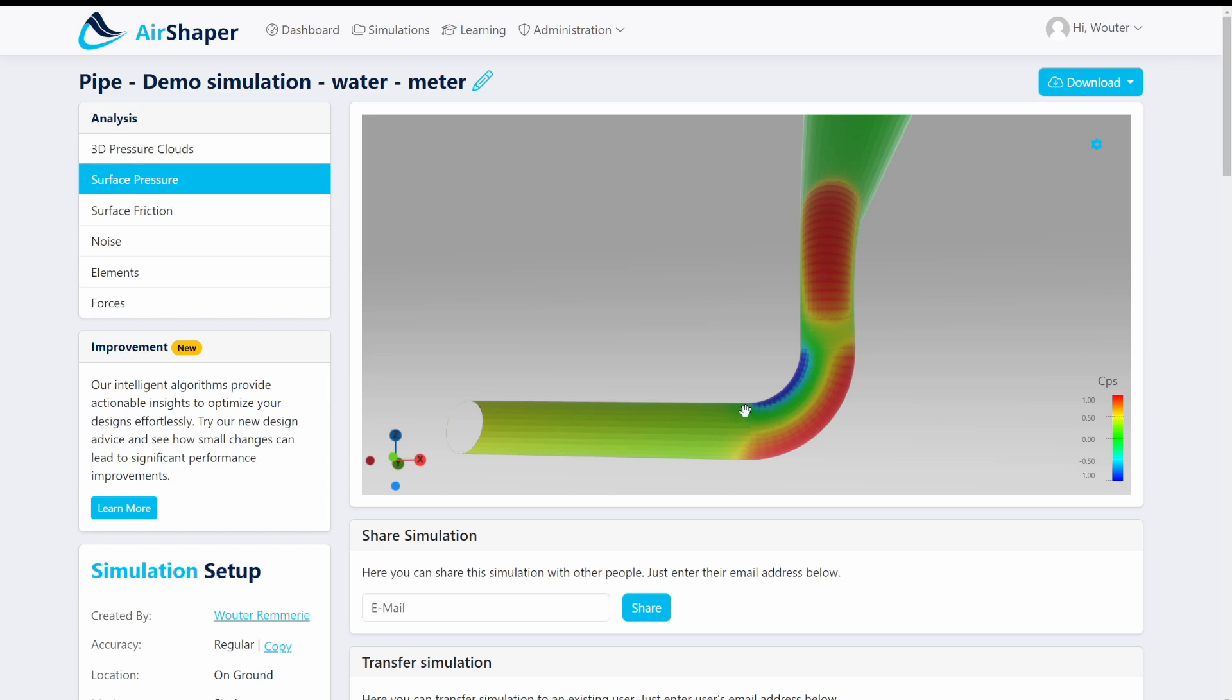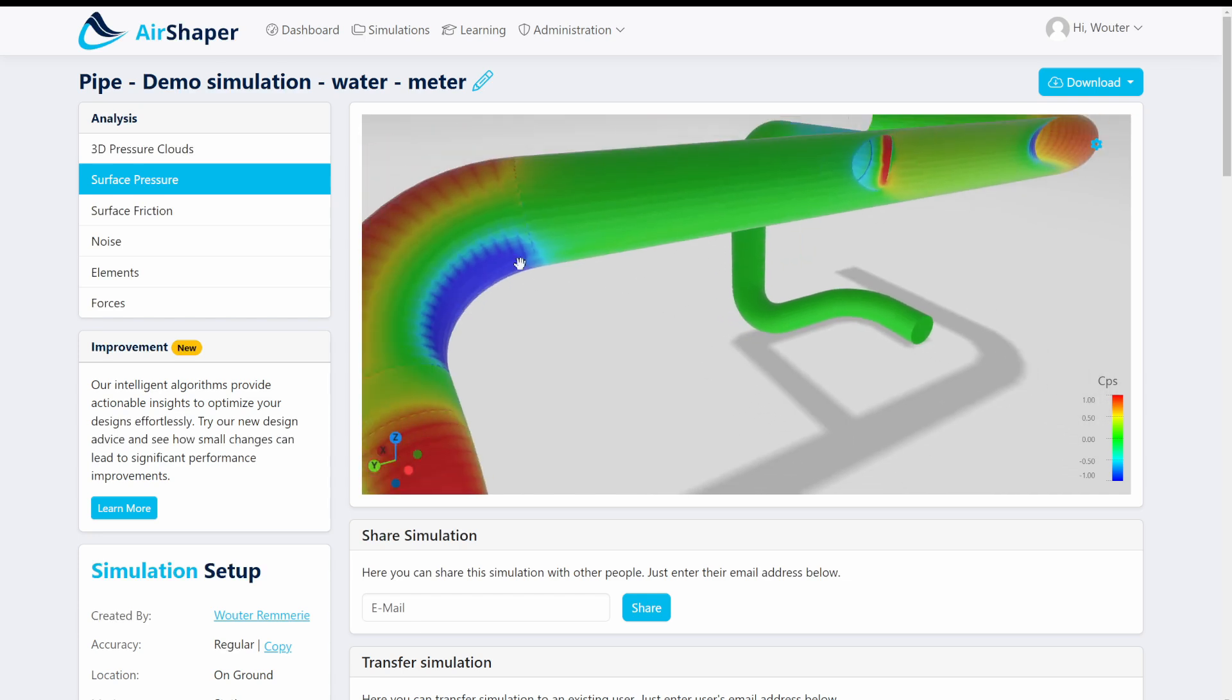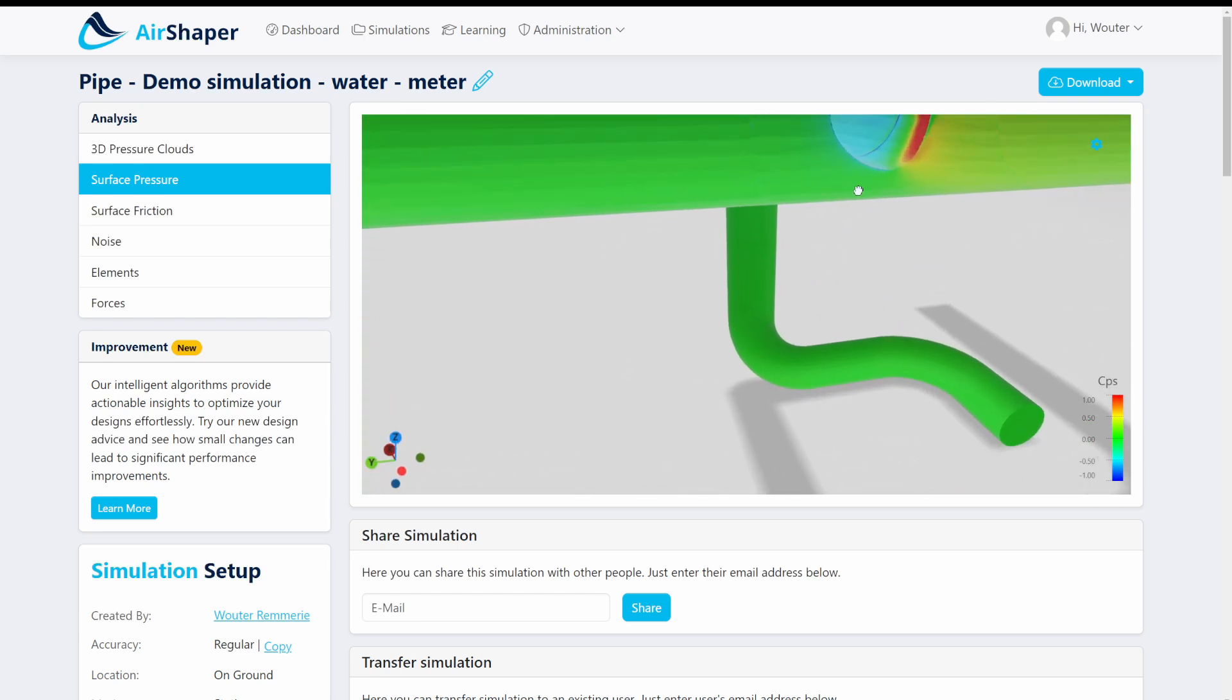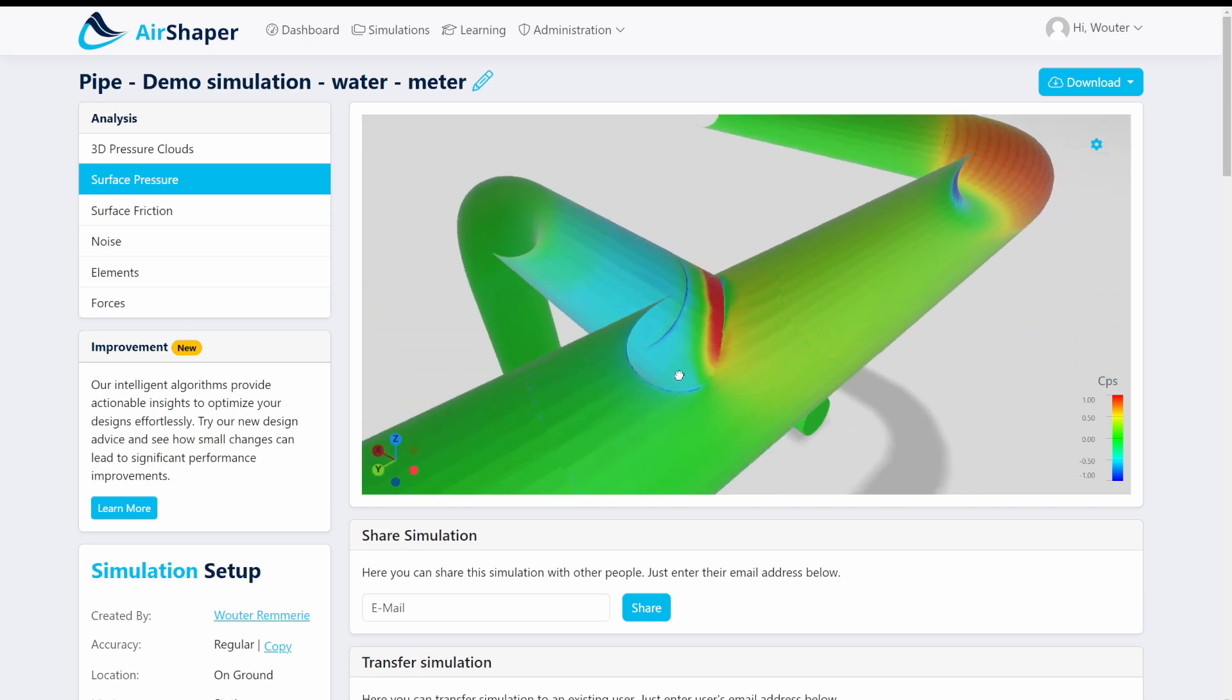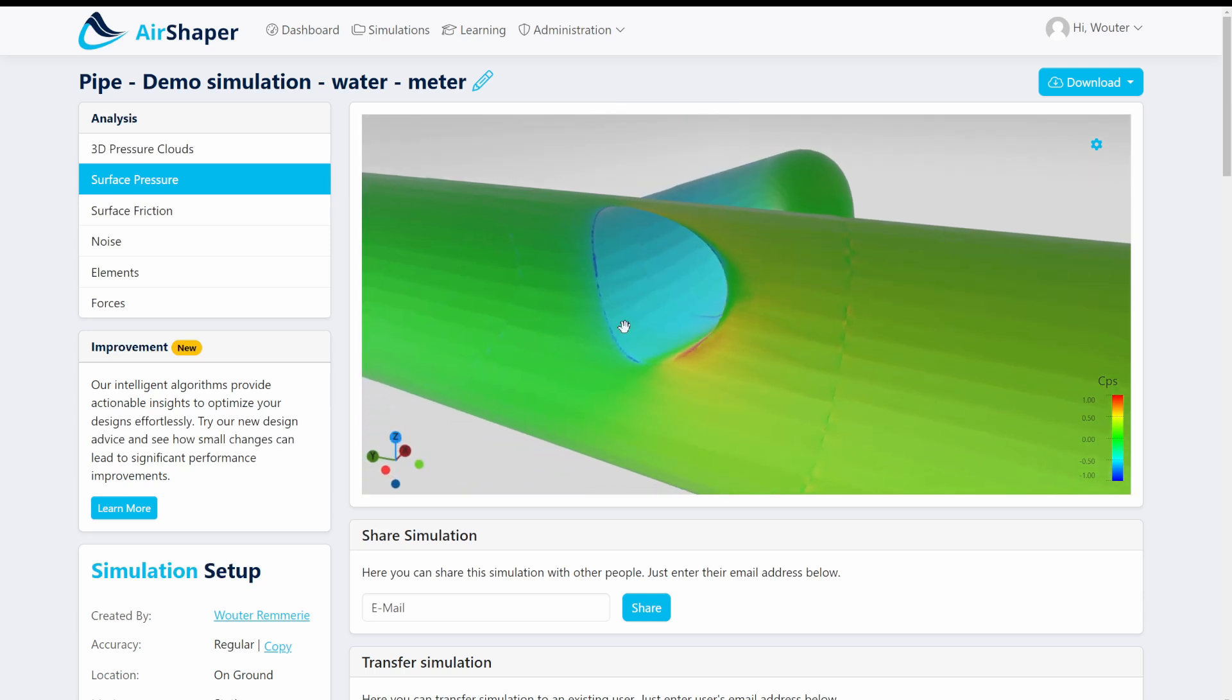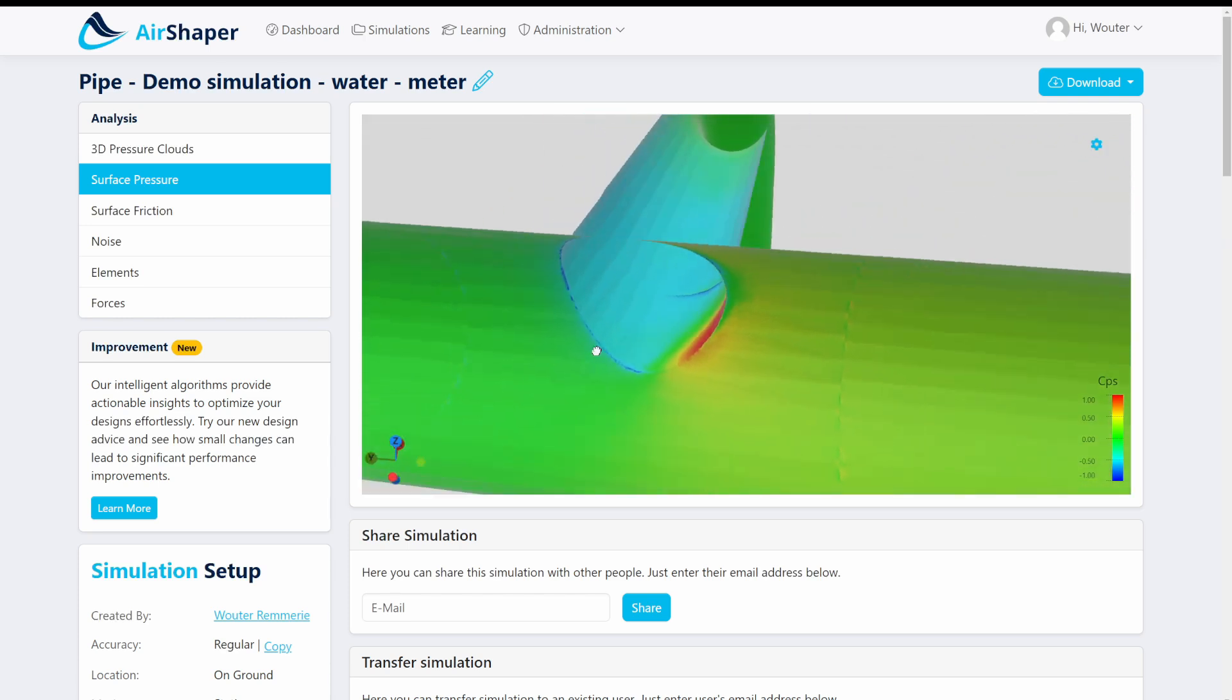The same with this bend so high pressure on the outside, low pressure on the inside and here this is also something that we saw so this is the large radius that the flow is following and it actually hits the side here of this junction and that's why some of the flow is forced this way. You can also see that we have these dark blue rings this is because there's this very small edge in the 3D model between these different pipe elements and this creates a local drop in pressure as the air speeds up around that edge.